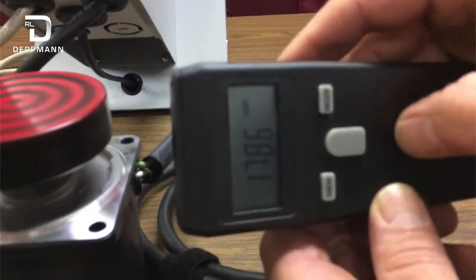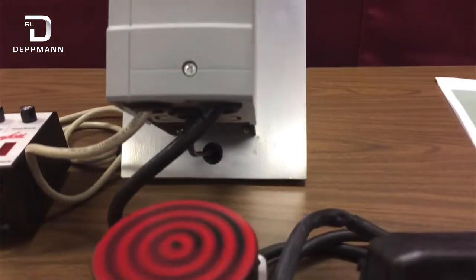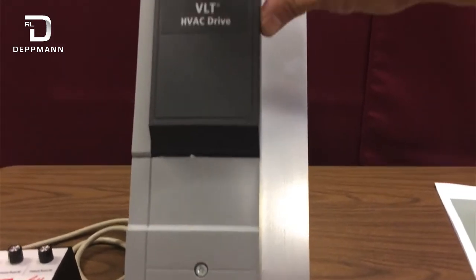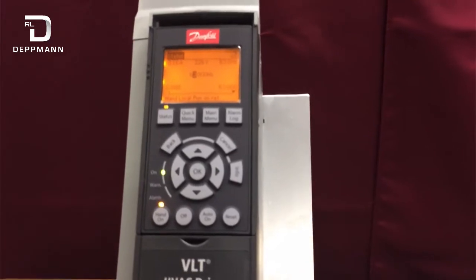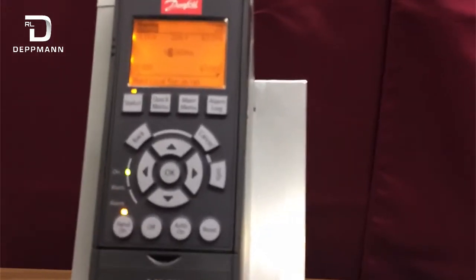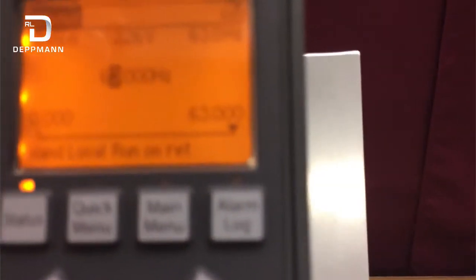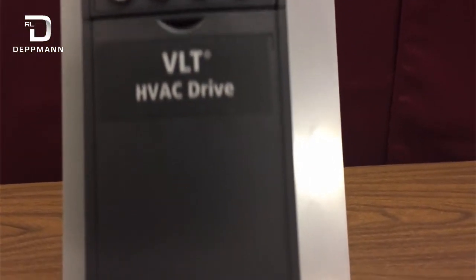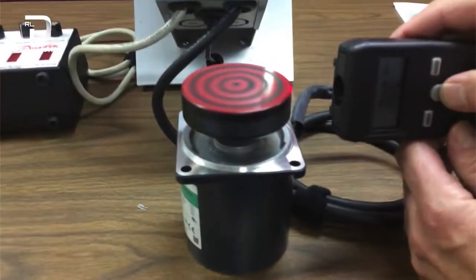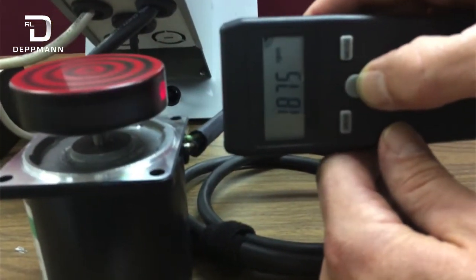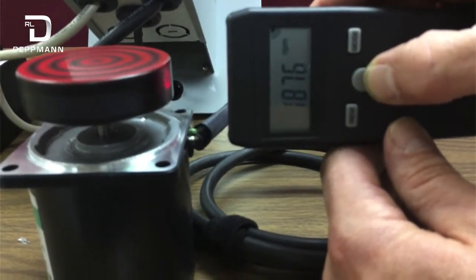Now I'm going to go back and go up just a little bit more to that new maximum that we set, 63 Hz. Now if we look at the motor running with our tachometer, we can see the speed is 1876.